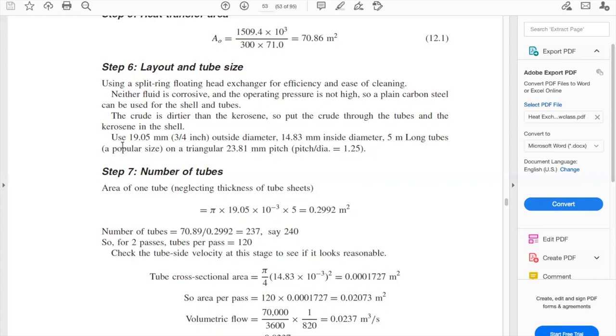These are the specifications the book provides based on these tubes being readily available. We use a triangular pitch because the crude, the dirtier fluid, goes inside the tubes. Outside the tubes you will have kerosene, which is not as dirty. With a triangular arrangement it will not be that difficult to clean, even though the tubes are close together. Everything you propose for your design should have reasoning behind it: triangular pitch accommodates more tubes, and the dirtier fluid stays inside, leaving the cleaner fluid outside for easier maintenance.